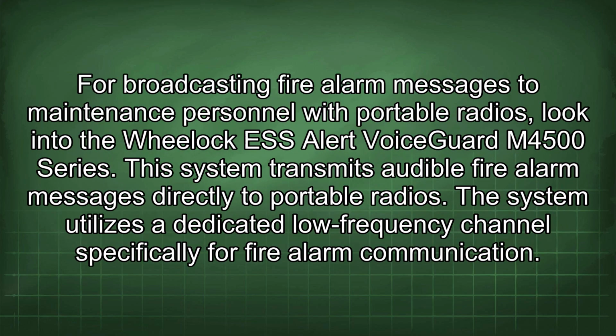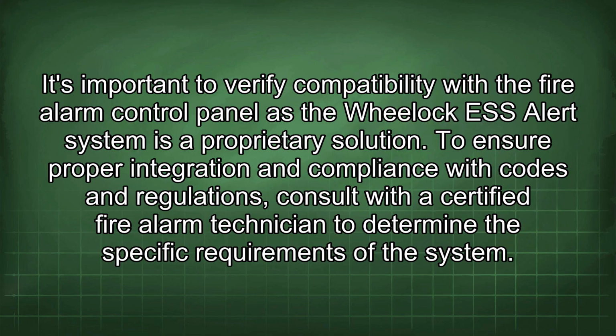For broadcasting fire alarm messages to maintenance personnel with portable radios, look into the Wheelock ESS Alert Voice Guard M4500 series. This system transmits audible fire alarm messages directly to portable radios, using a dedicated low-frequency channel specifically for fire alarm communication. It's important to verify compatibility with the fire alarm control panel, as the Wheelock ESS Alert system is a proprietary solution. To ensure proper integration and compliance with codes and regulations, consult with a certified fire alarm technician to determine the specific requirements of the system.